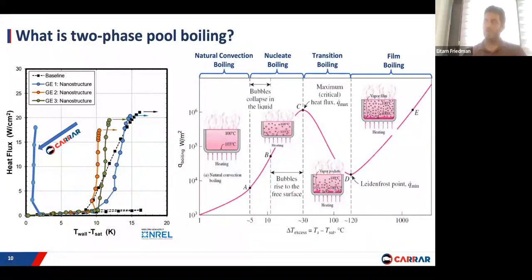Here we have a higher heat transfer coefficient because we can handle higher heat fluxes. But in cooling, and also in the battery use case, we want to be somewhere between B and C. There we already have bubbles coming up to the surface, and we're taking full advantage of latent heat, so we can apply a full two-phase pool boiling solution to the batteries.